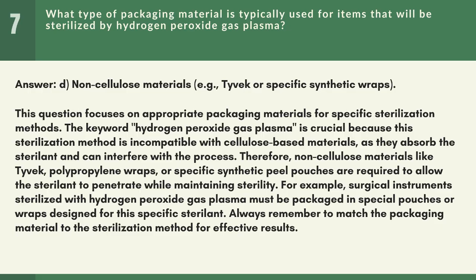Therefore, non-cellulose materials like Tyvek, polypropylene wraps, or specific synthetic peel pouches are required to allow the sterilant to penetrate while maintaining sterility. For example, surgical instruments sterilized with hydrogen peroxide gas plasma must be packaged in special pouches or wraps designed for this specific sterilant. Always remember to match the packaging material to the sterilization method for effective results.